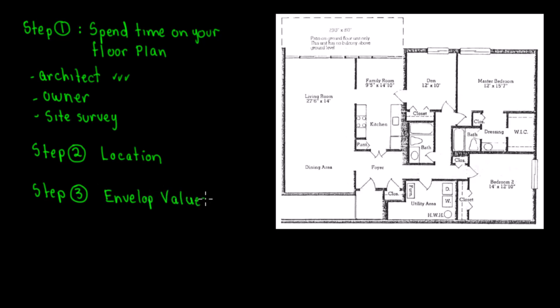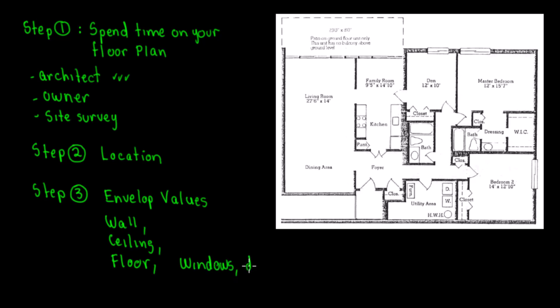The envelope values cover wall, ceiling, floor, windows, and doors. What we need specifically are the U-values — the U-factor. There's another video covering U-factor and insulation values. You also need the Solar Heat Gain Coefficient. The reason location comes first is because you need to know the International Energy Conservation Code (IECC) requirements for that location.